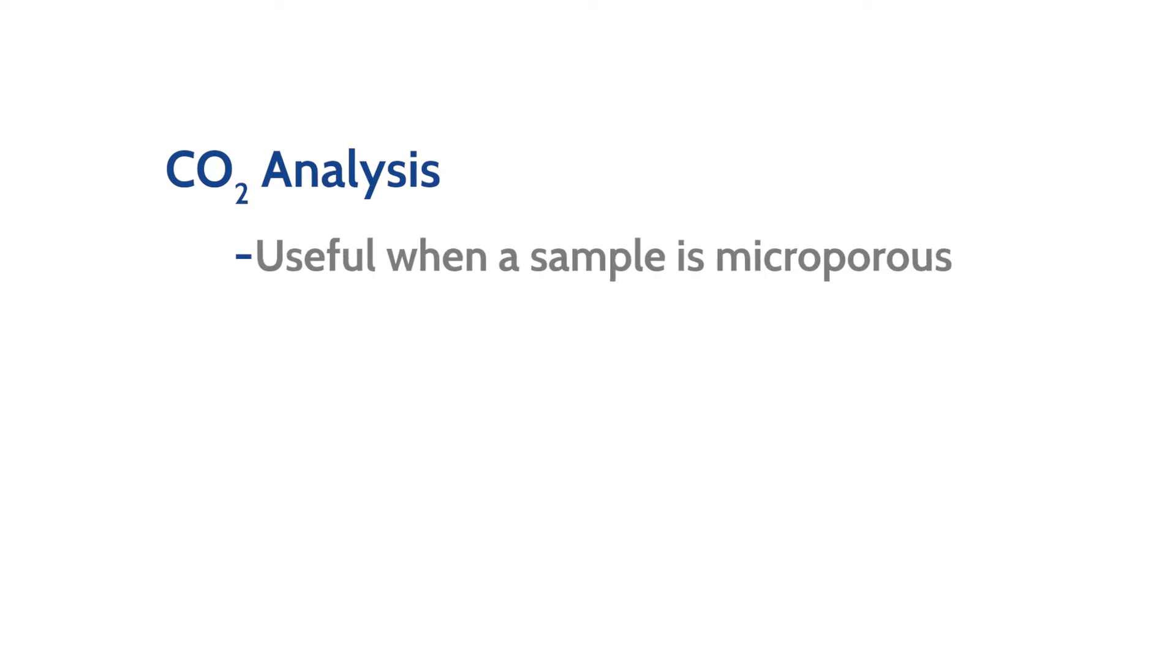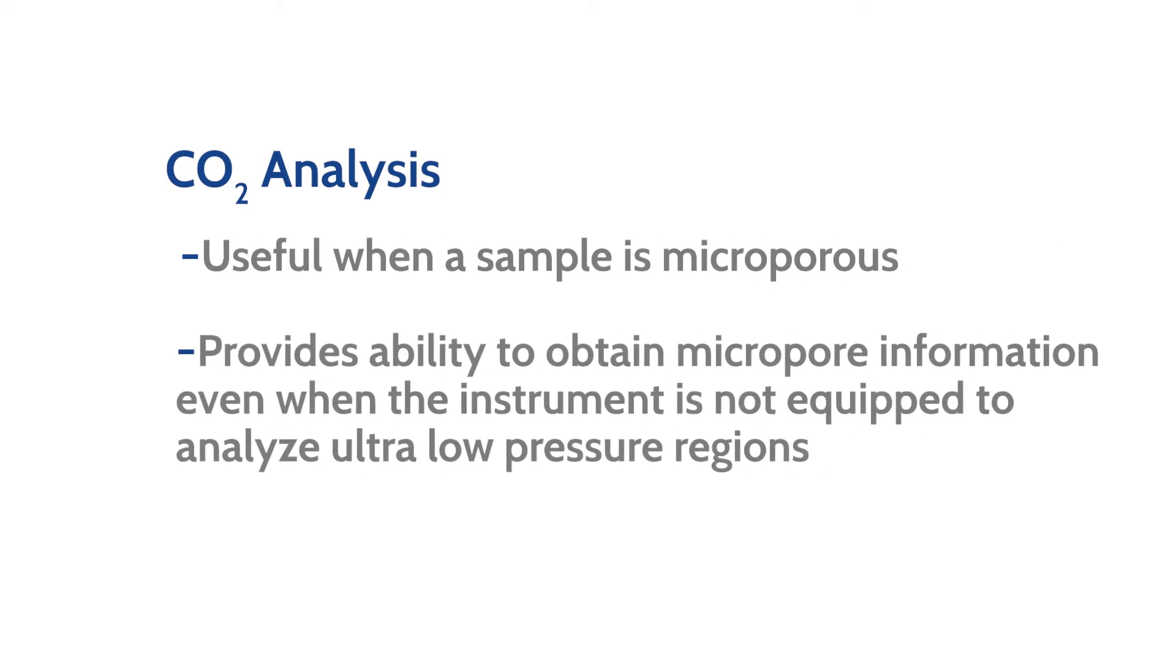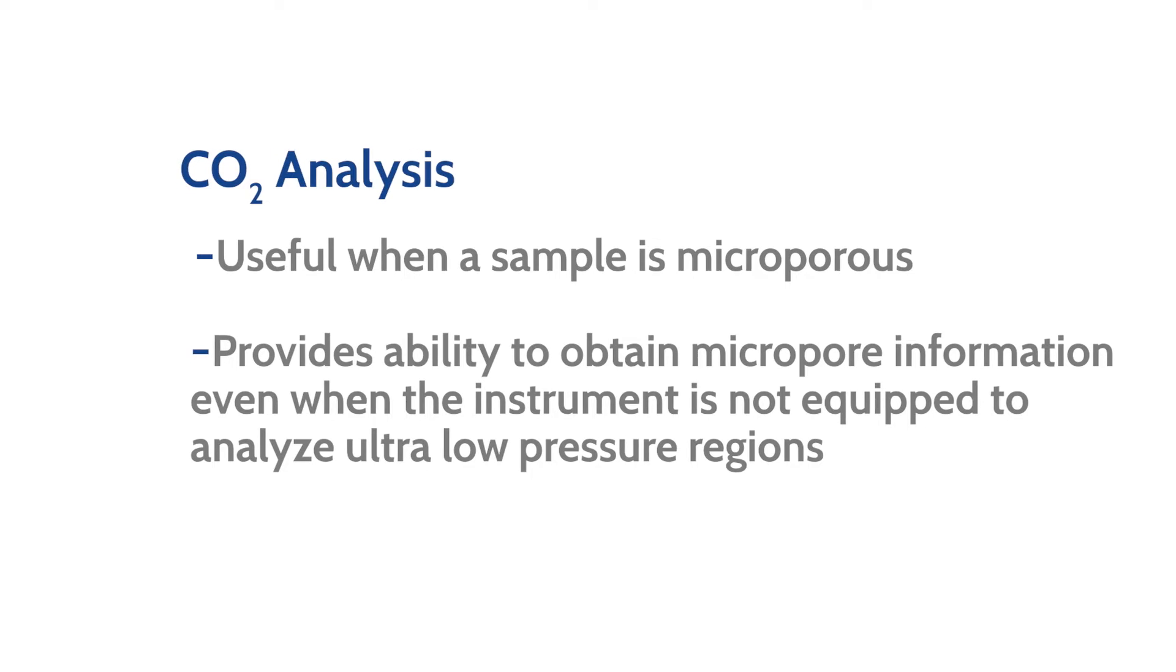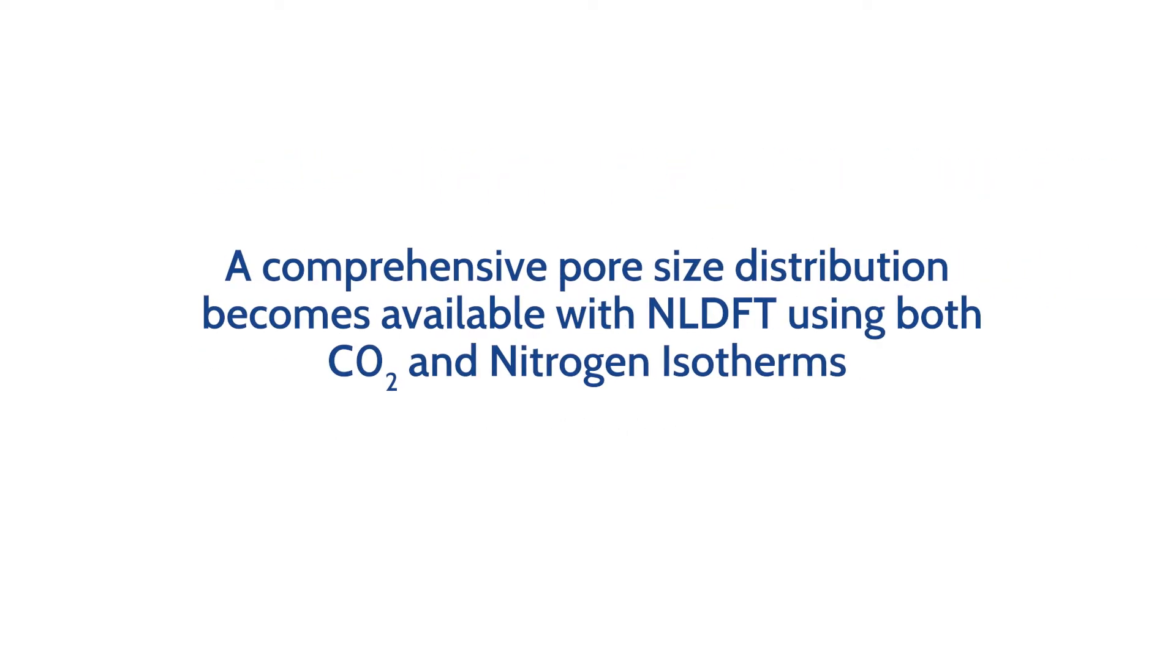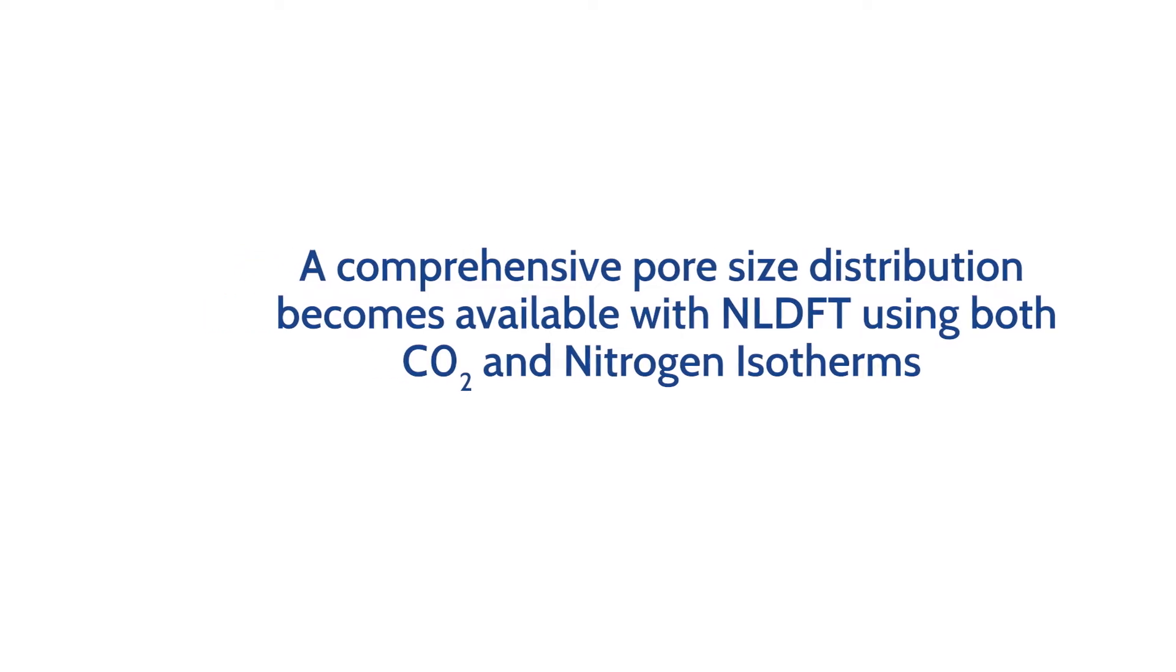CO2 analysis is useful when a sample is microporous. It provides the means to obtain micropore information even when the instrument is not equipped to analyze the ultra-low pressure region. A comprehensive pore size distribution becomes available with the NLDFT using CO2 and nitrogen isotherms.